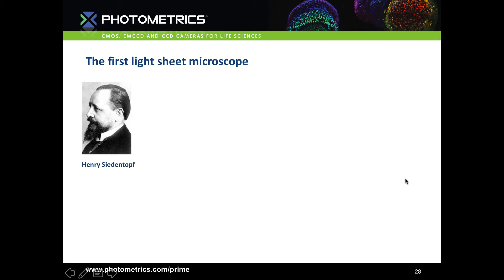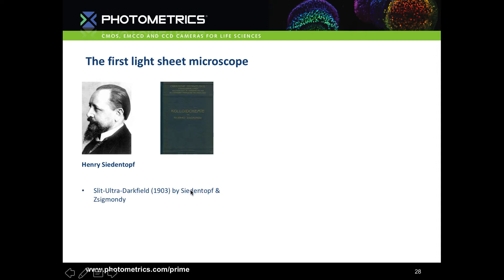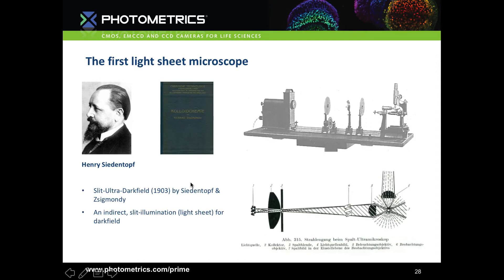Lightsheet feels like a new technique, but it was actually invented back in 1903 by Siedentopf and Zsigmondy, who published what we would now call an ultramicroscope. It's an indirect slit illumination used for darkfield, but it uses exactly the same principle — light comes in from the left, passes through lenses, hits the illumination objective casting the lightsheet onto the sample, and is detected through the detection objective. The beam converges at the centre and diverges out again to form the lightsheet.